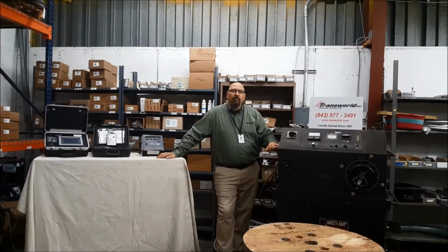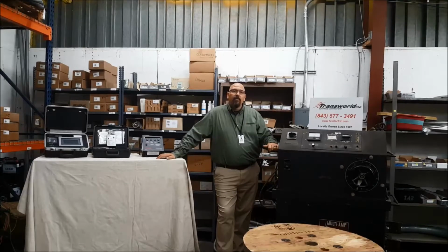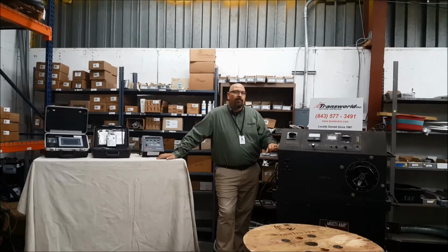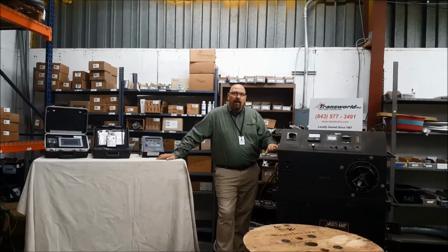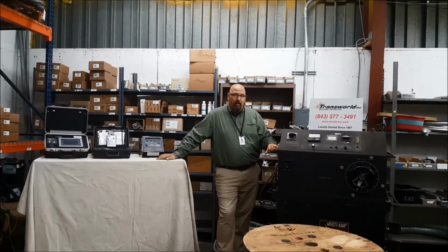The purpose of injection test sets is to test the different and separate trip functions of breakers, depending on if they are a magnetic, thermomagnetic, or digital trip unit. The different functions that we would be testing are long time and short time, which are your overcurrent protection functions, instantaneous, which is your short circuit protection, and your ground fault function, which is your ground fault current protection.